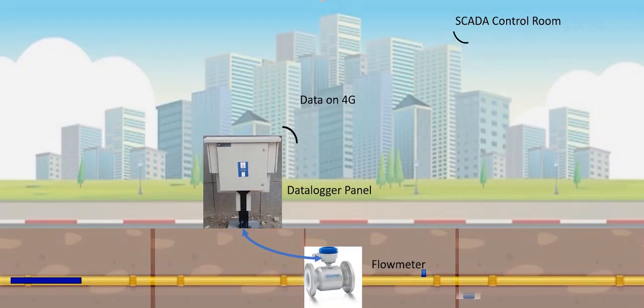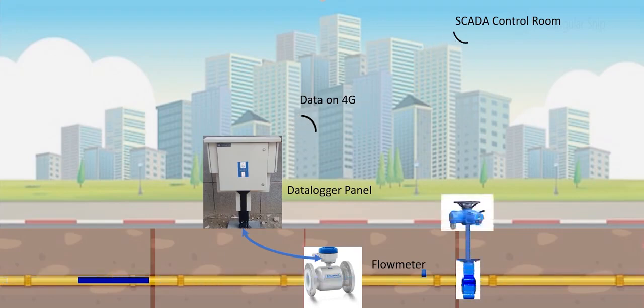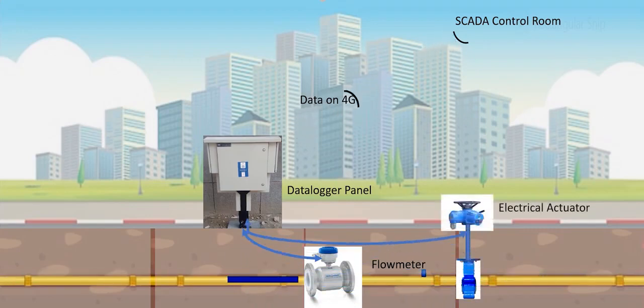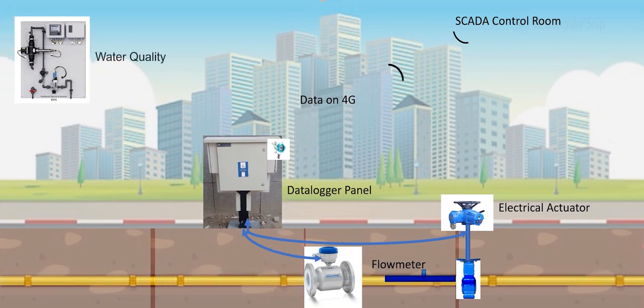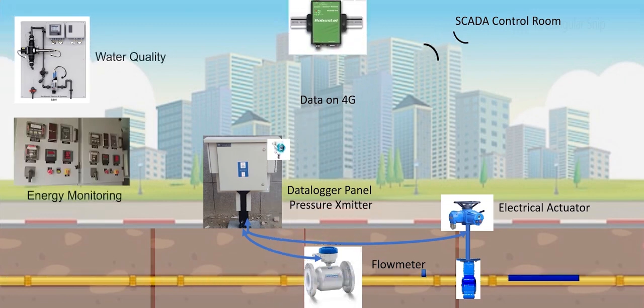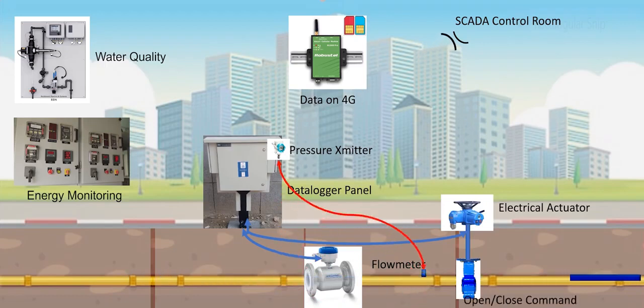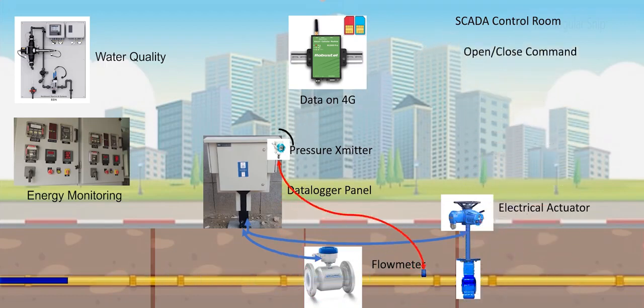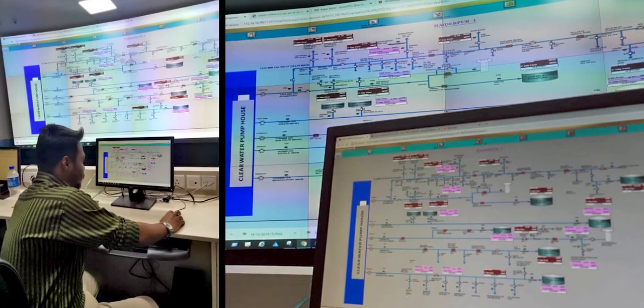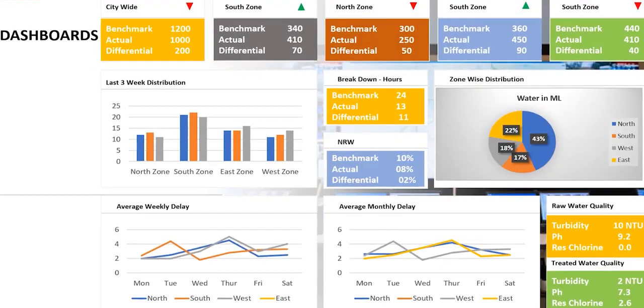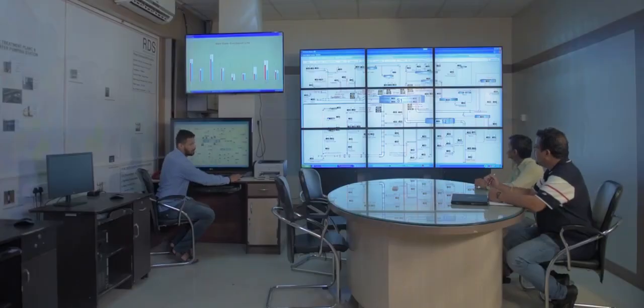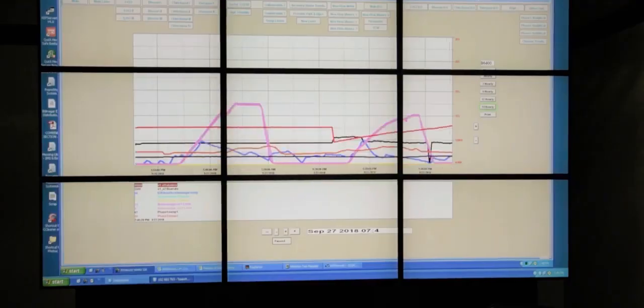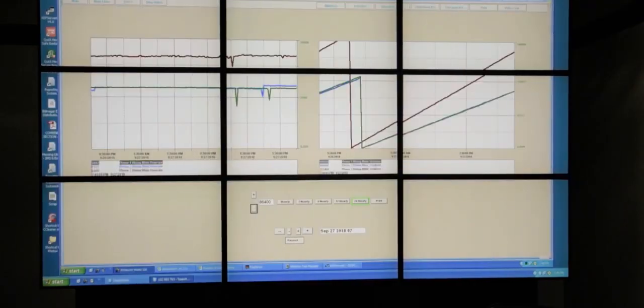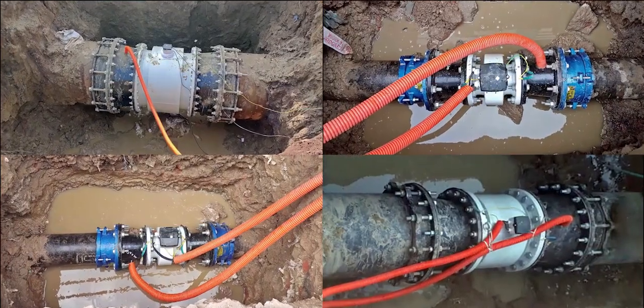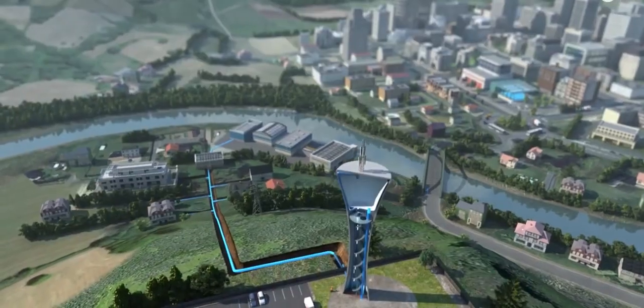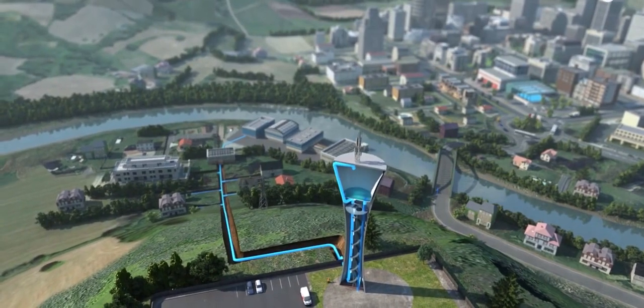RTU and data logger panels shall transmit data, that is flow, pressure, water quality, valve position and energy, through 4G modems to the central and zonal SCADA centers. This data shall be analyzed using analytical software to assist the municipal engineers to identify leakages, unauthorized supply and tappings, track and measure UFW and ensure equitable distribution to all parts of Vadodara.